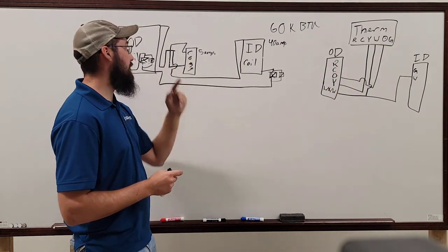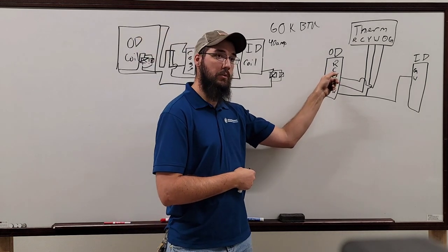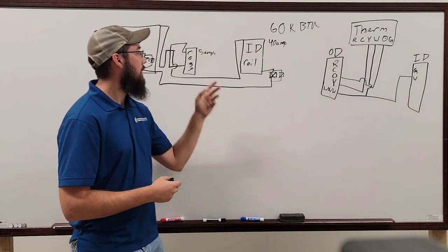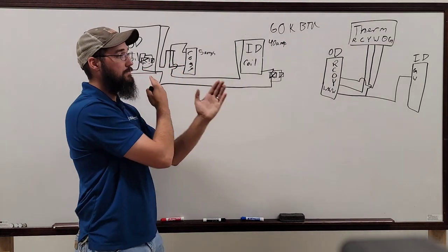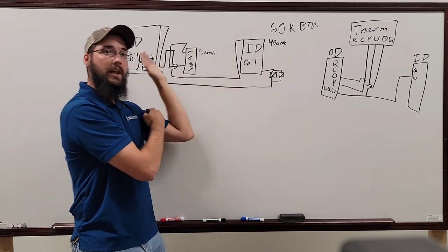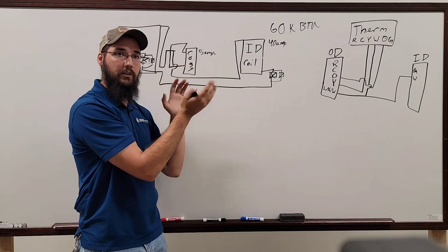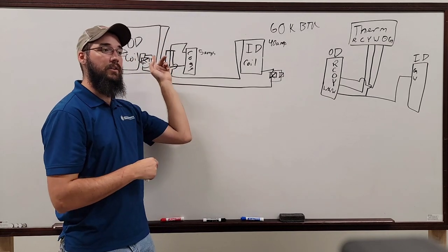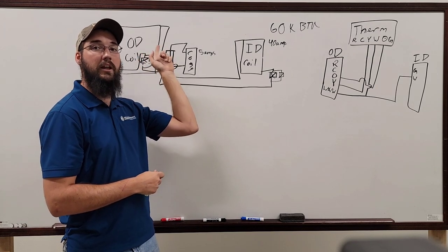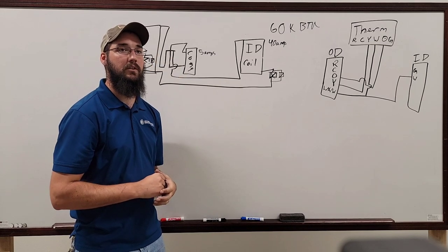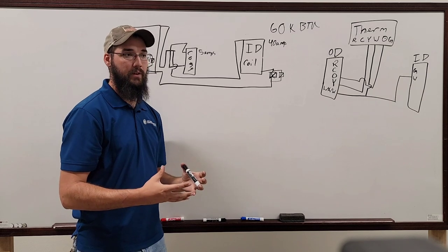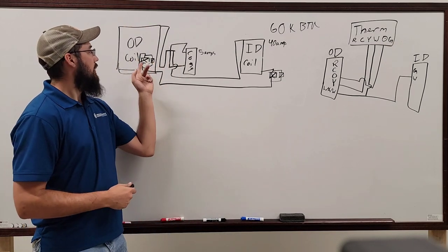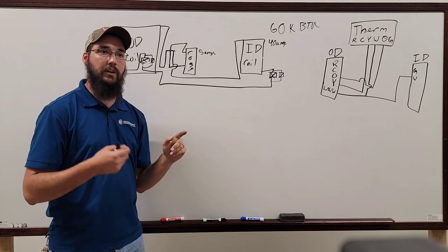And when it does, you're going to hear the reversing valve cycle on its own. We never got a signal from O. Okay? Thermostat never asked for this. This is all happening internally at the outdoor unit. And so what it does, it literally flip-flops them, and the indoor coil begins to cool again. The outdoor coil begins to become the condenser again, and it runs in cooling mode to heat up the outdoor coil to defrost it. Now, what'll happen at the same time is your outdoor fan relay will trigger, and your fan will shut off when you're in defrost, so that you build heat and defrost faster, instead of having 30 degree air flowing across the coil you're trying to get all the ice off of. So that's an immediate indicator that you're in defrost.